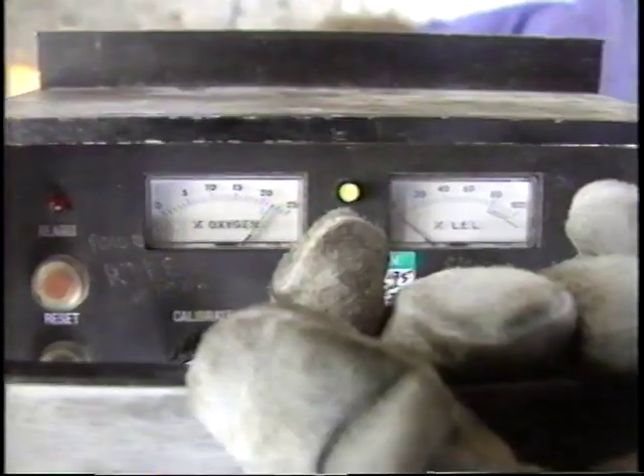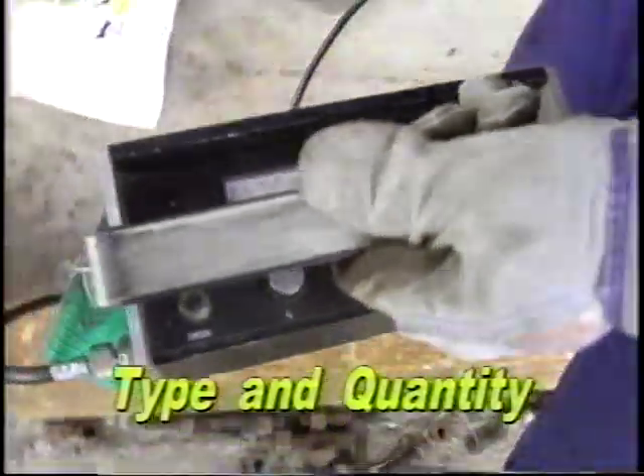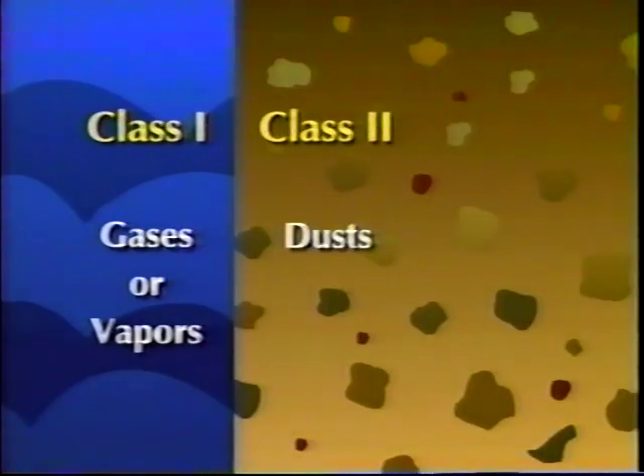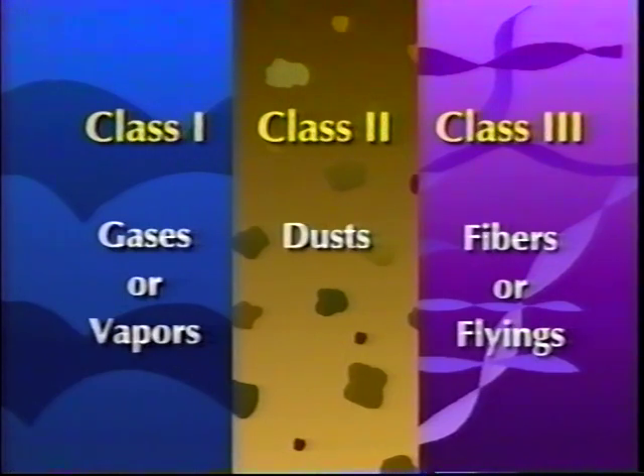The traditional NEC method classifies hazardous locations based upon the type and the quantity of ignitable material present. There are three classes. Class 1 has explosive or flammable gases or vapors. Class 2 has combustible dusts. Class 3 has ignitable fibers or flyings. You must select the equipment that is rated for the class of hazard present.